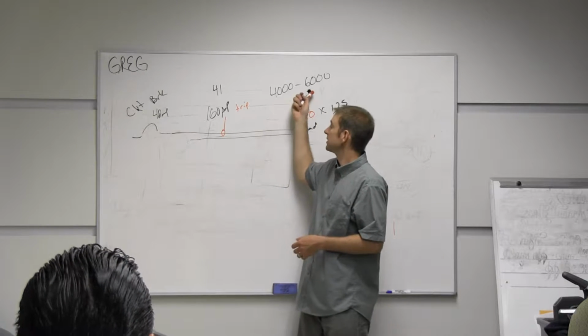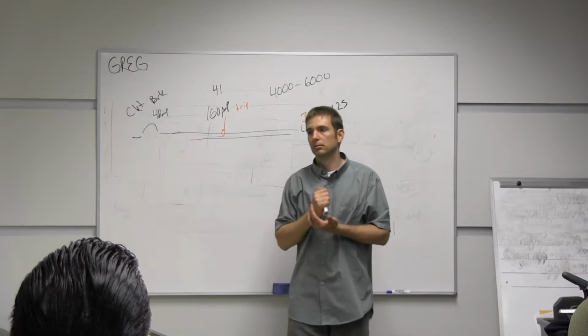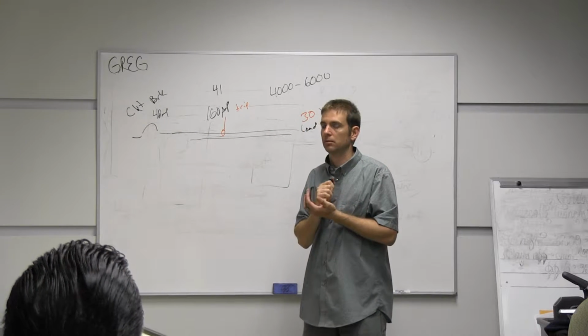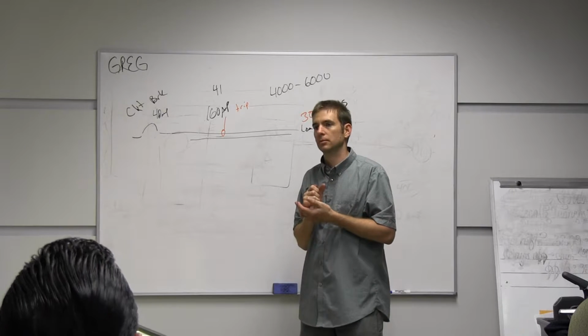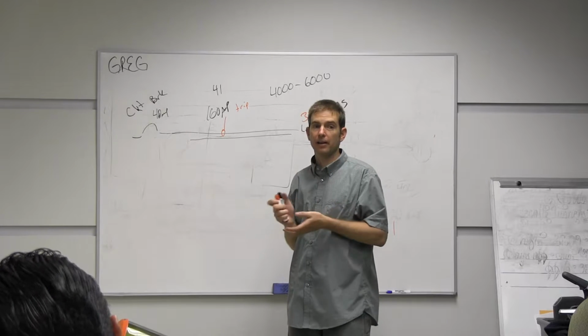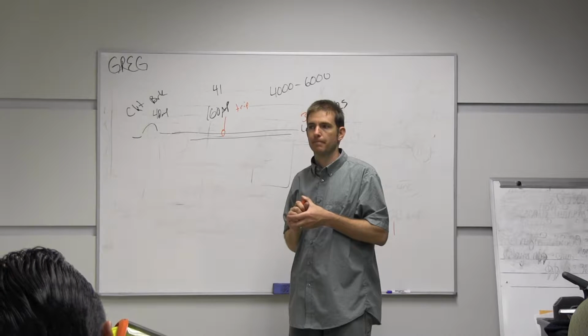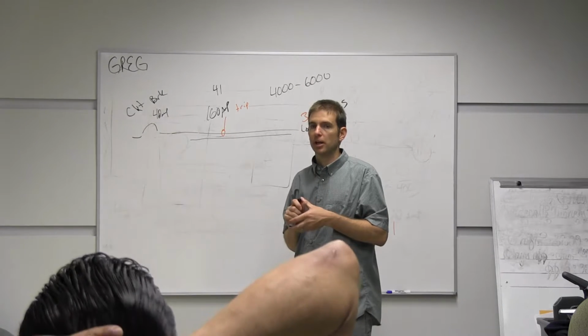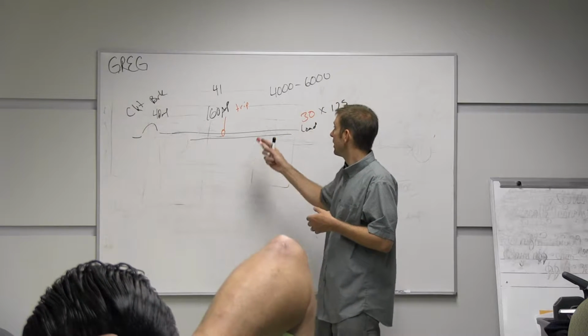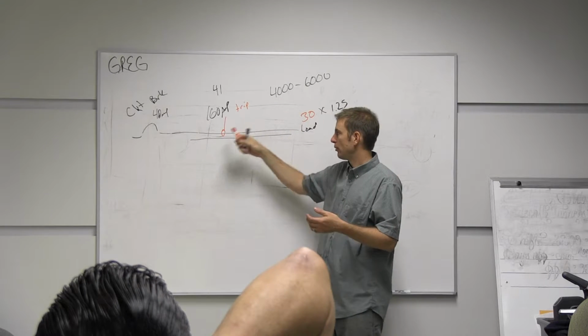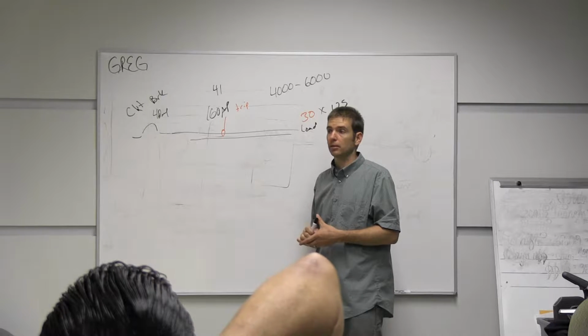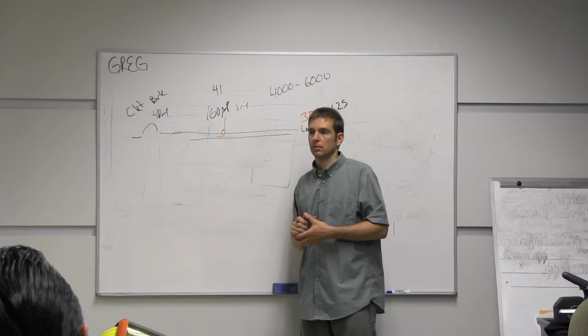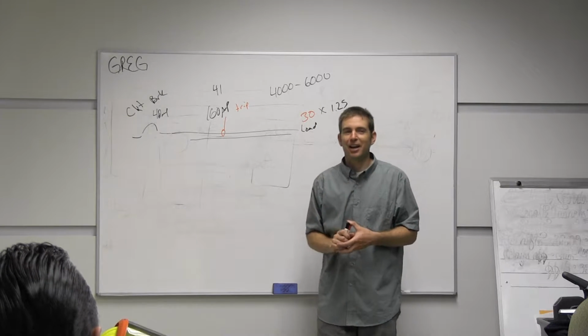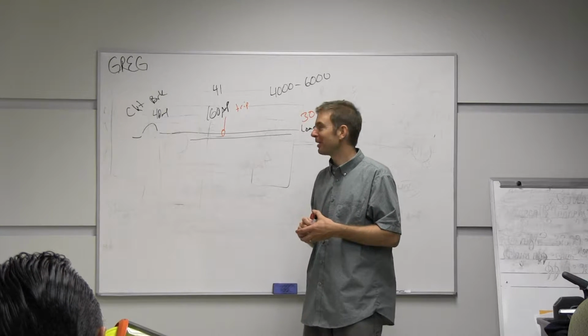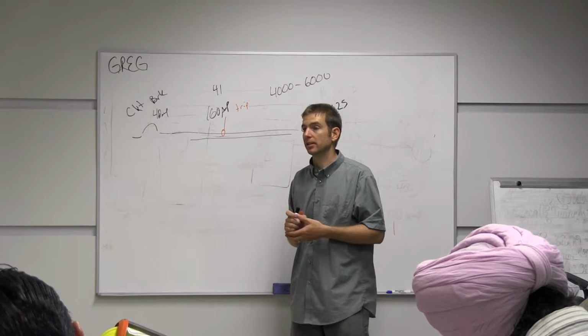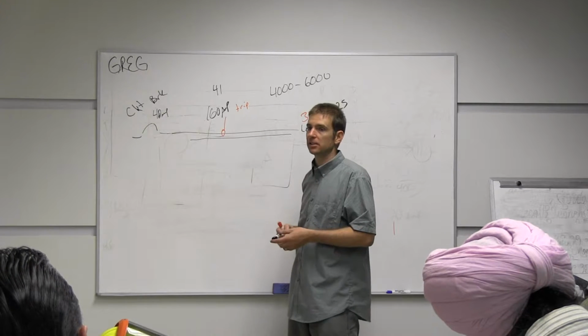Wow. So about 4,000 to 6,000 amps would do that. So how are we putting 4,000 to 6,000 amps on a 40 amp circuit breaker? I never mentioned this: how fast does electricity travel? Essentially it's the speed of light, which is 186,000 miles per second. So we have electrons traveling the speed of light over a distance of, who knows, maybe a few hundred feet. That's pretty quick. How fast does a circuit breaker trip? Probably slower than that. Circuit breakers don't travel the speed of light yet. I don't know if they ever will. They trip pretty much instantaneously. They trip fast, but not as fast as the speed of light or as fast as electrons.